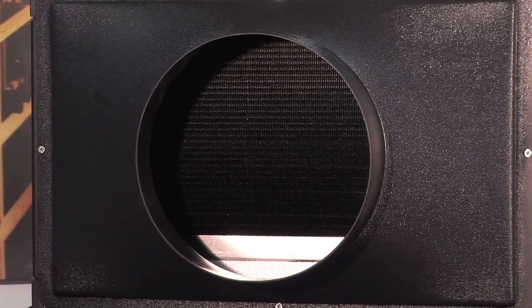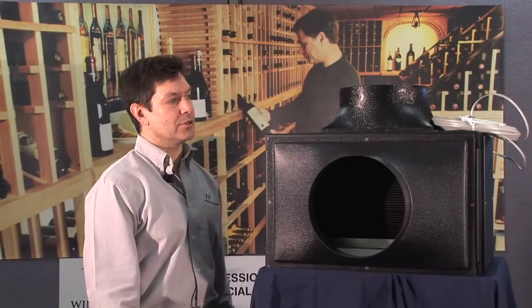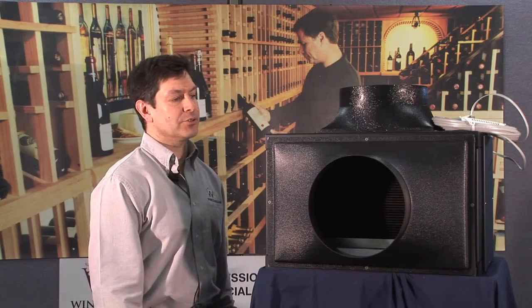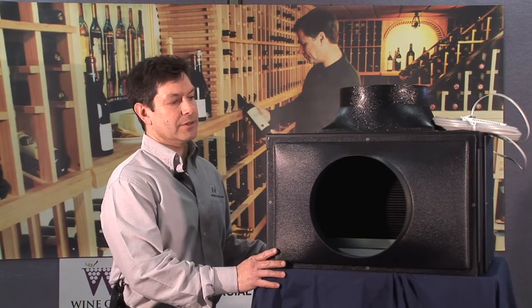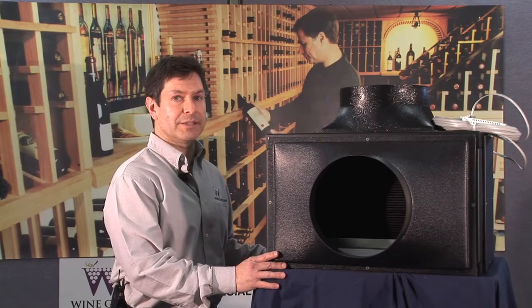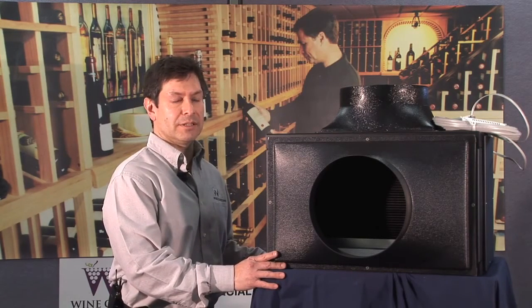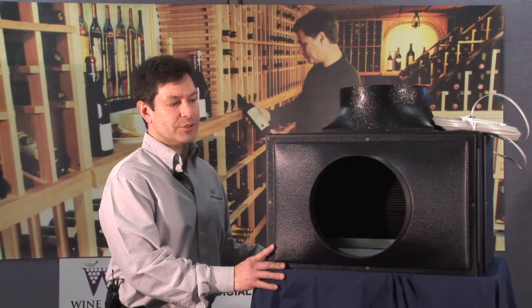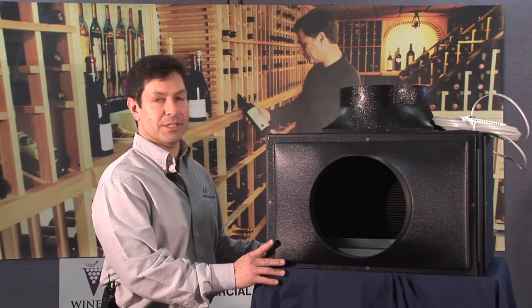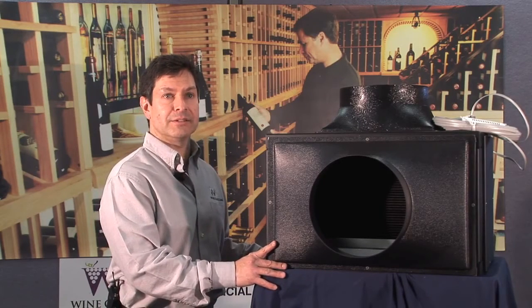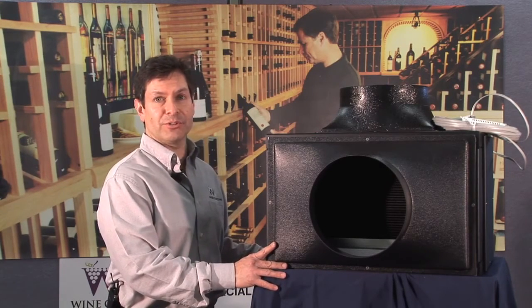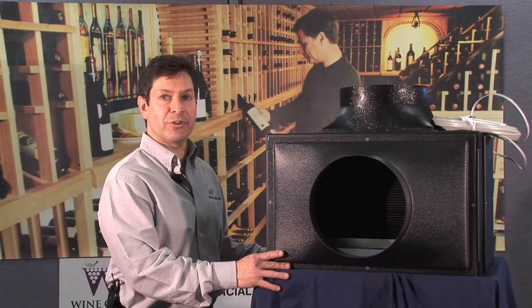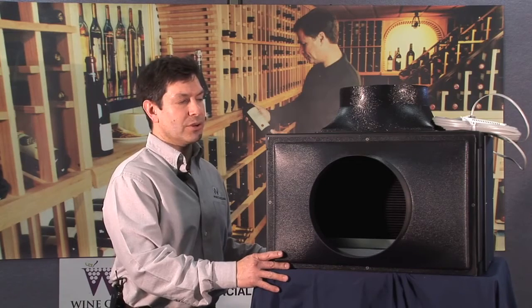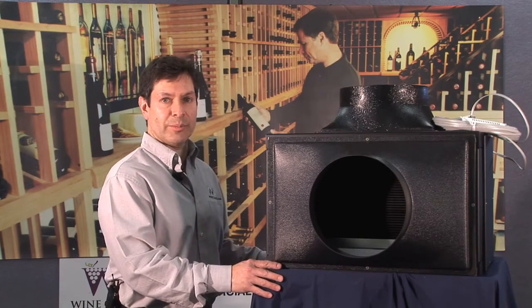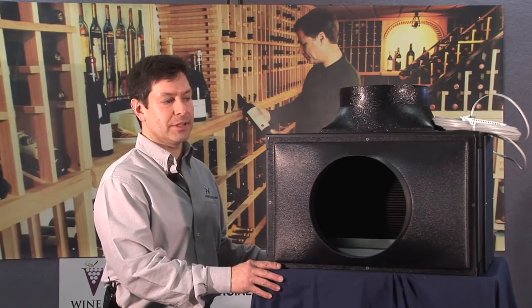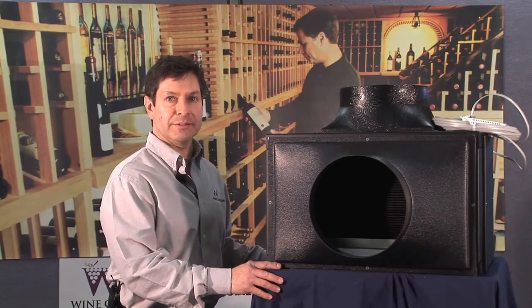I talked about the split system being the ultimate in flexibility. It's probably the quietest system that we manufacture. The fan coil unit, fully ducted, is extremely quiet, especially mounted outside of the wine cellar, above or below. You're dealing with flexible ductwork to and from this unit, and all you're seeing inside the wine cellar would be supply and return grills and hearing maybe some air noise. There's no compressor, no condenser. All of that mechanical equipment is mounted out away from the system with just interconnecting piping.